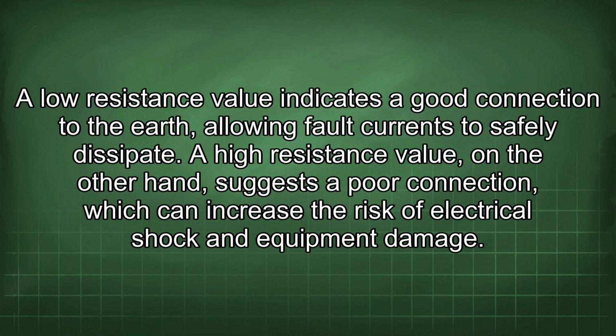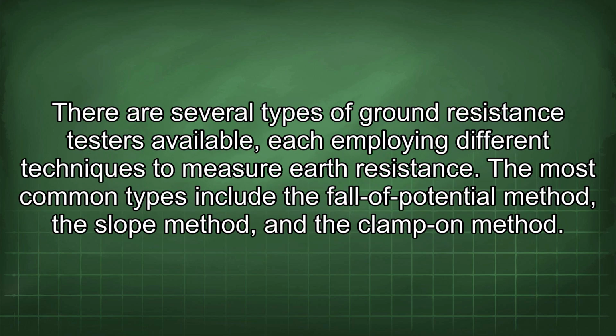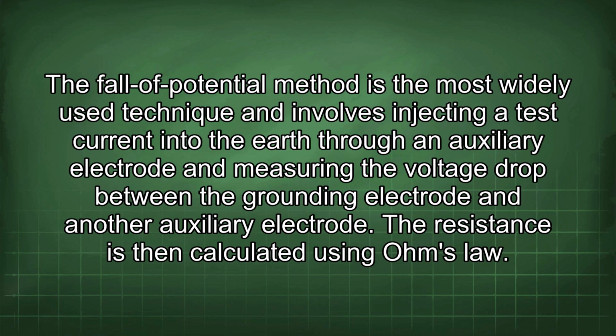A high resistance value, on the other hand, suggests a poor connection which can increase the risk of electrical shock and equipment damage. There are several types of ground resistance testers available, each employing different techniques to measure earth resistance. The most common types include the fall-of-potential method, the slope method, and the clamp-on method. The fall-of-potential method is the most widely used technique and involves injecting a test current into the earth through an auxiliary electrode and measuring the voltage drop between the grounding electrode and another auxiliary electrode. The resistance is then calculated using Ohm's law.